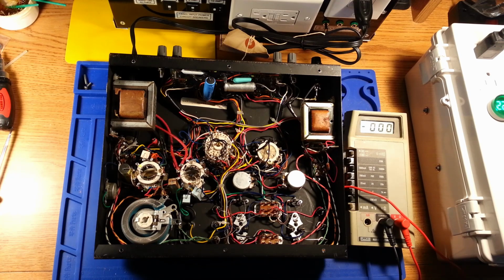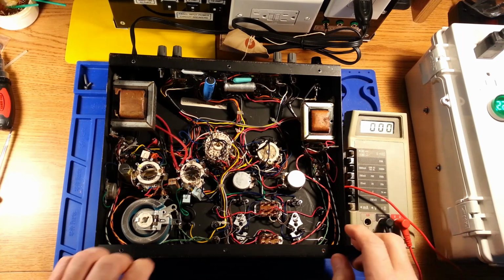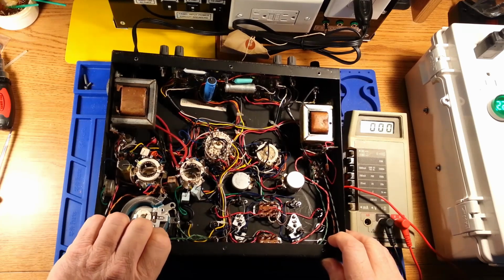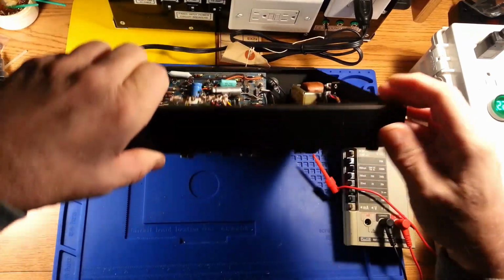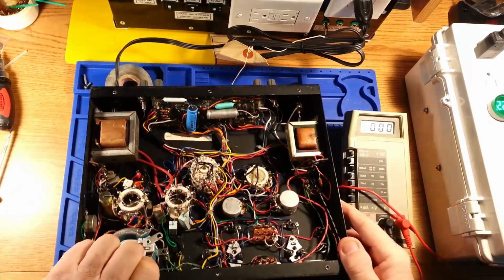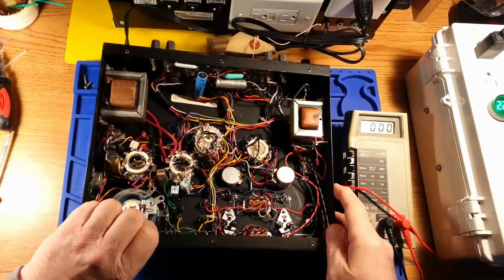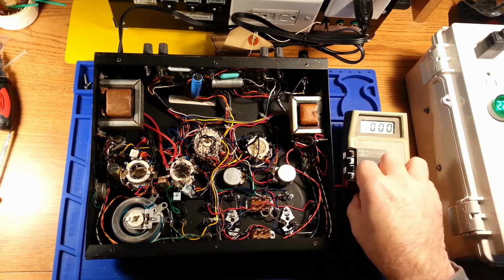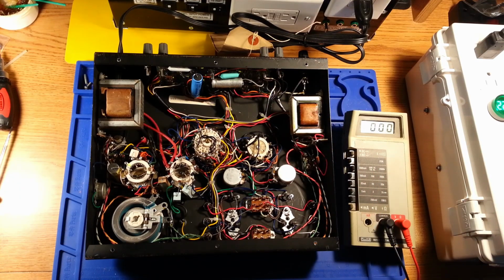And I'm going to start off by testing the low voltage transformer. There are 2 transformers in this unit. One's a low voltage. I think it's only maybe 6 volt, 12 volt AC output. We're going to check that level for sure. My power switch is currently off on the equipment. I'm going to roll a tape in here to level things out a little bit because it's wobbling around a lot. And I'm just going to check the secondary voltage on that transformer. I did check the fuse. The fuse is of a proper reading and not blown.